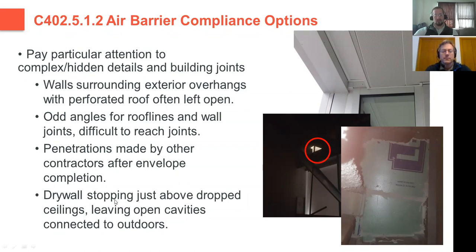Another thing to be aware of that we see very commonly is drywall stopping just above drop ceilings, especially on exterior walls. It leaves an open pathway for anything entering that wall cavity to then leak into the inside of the building. Again, because ceiling plenums are often used as returns for HVAC systems, they're depressurized slightly, and so that draws in outside air directly into the building.